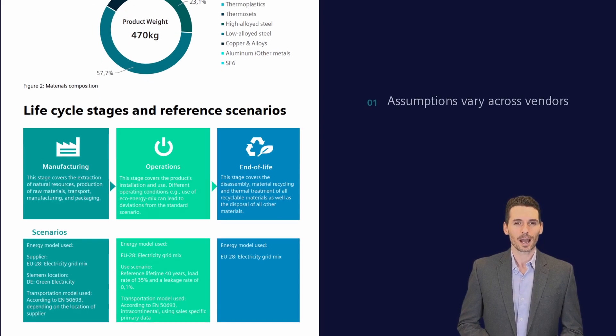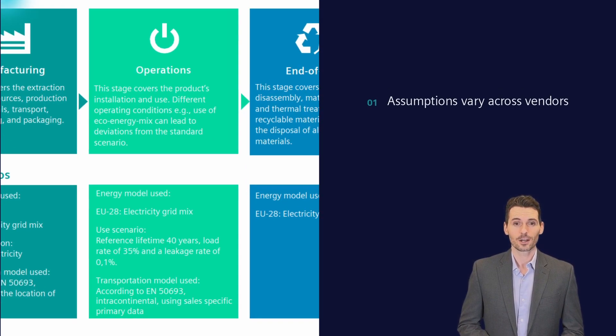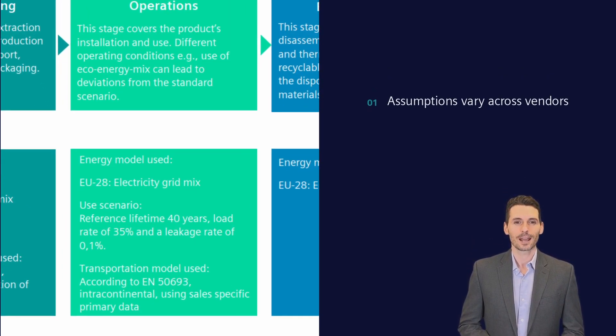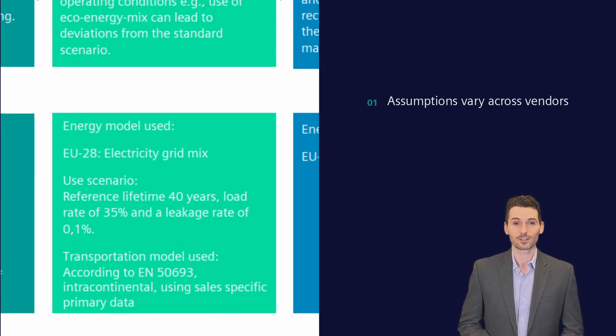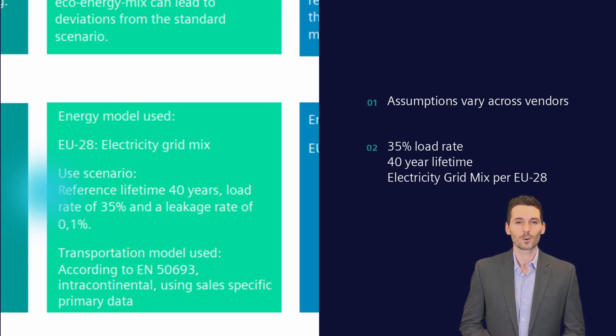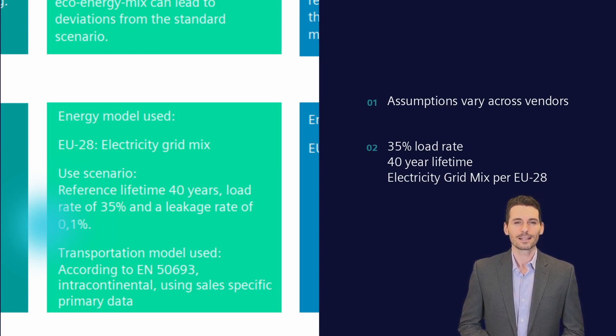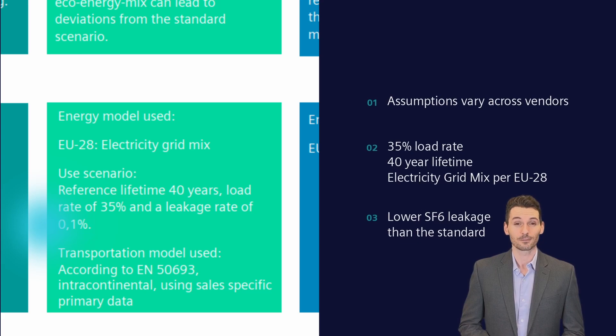Since the underlying assumptions may vary from vendor to vendor, it is critical to understand these differences when analyzing EPDs across manufacturers. Siemens has chosen operating assumptions based on decades of experience across a diverse global footprint, including a 35% load rate, an equipment lifetime of 40 years, an electricity grid mix as per EU28, and a 0.1% per year leakage per standard IEC 62271-1. It is important to note that the SF6 leakage from Siemens GIS is significantly lower than this standard value.